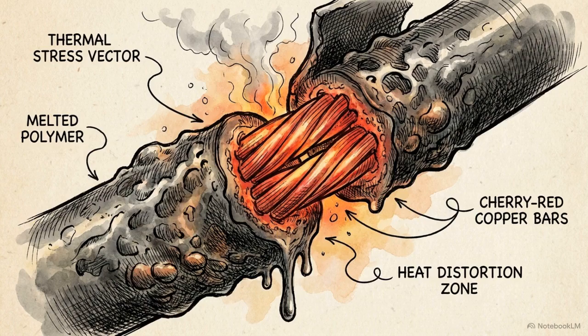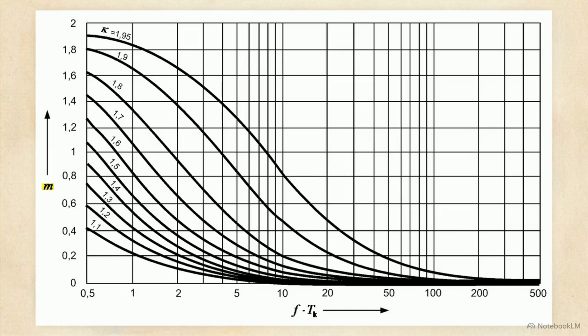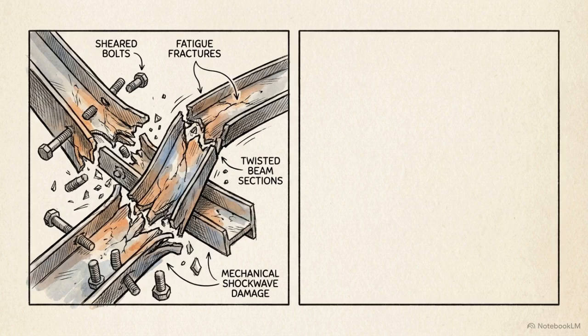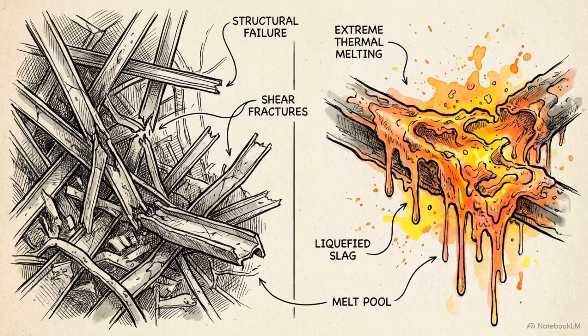As the asymmetrical wave pulses and decays over the next few cycles, it pumps extreme sustained heat into the surrounding hardware. This chart maps the M factor, plotting the time-dependent heat effect of the decaying DC offset. Engineers use this decay curve to calculate the Joule integral, a measure of total thermal energy, dictating exactly when copper wires melt and insulation ignites. An asymmetrical fault delivers a precise 1-2 punch.